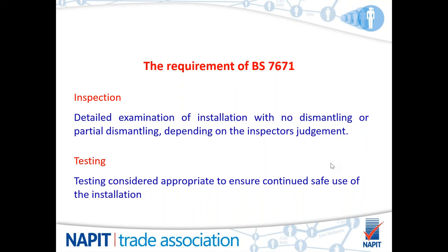It is not necessarily to the schedule that you would follow for initial verification. The testing is done to an installation that is mainly live and energized. So it is up to the inspector to ensure that they put the testing procedures in place that they need to ensure that the installation is safe.